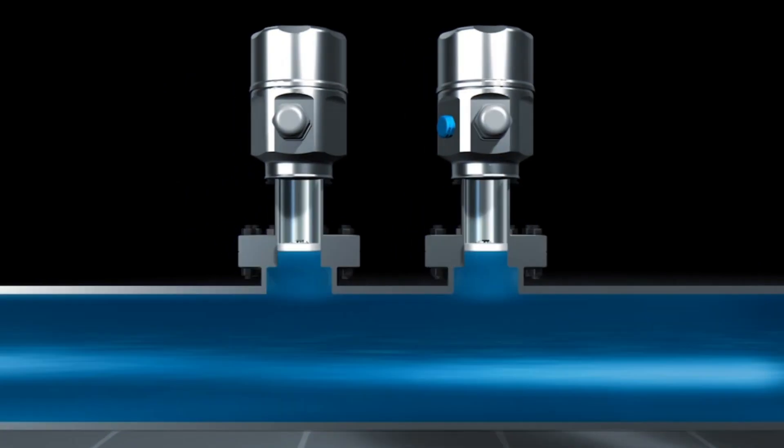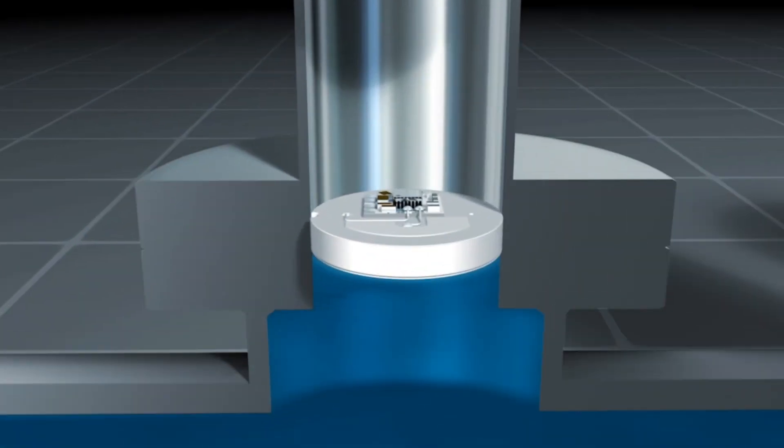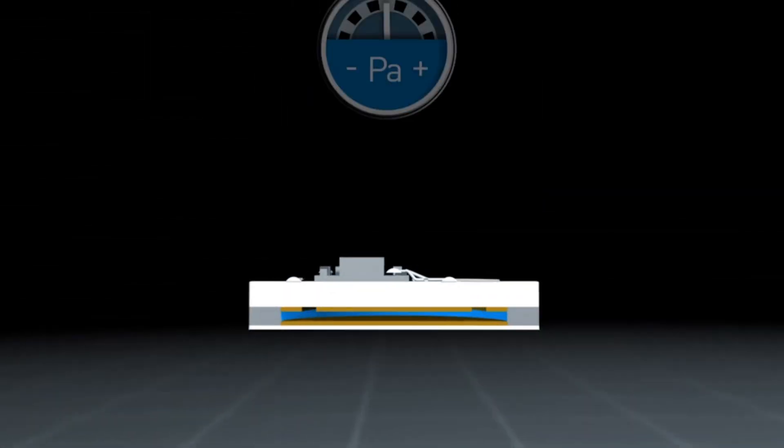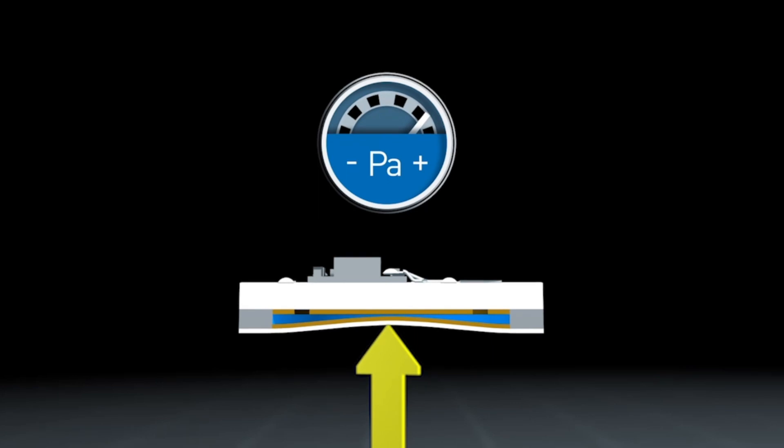Pressures can be measured continually in a pipe flooded with a liquid. We will have a closer look at the difference of an absolute pressure cell and a gauge pressure cell using the example of a ceramic cell. In a ceramic cell, an electrically conductive material is applied to a ceramic substrate, thus forming a capacitor. As pressure is applied, the diaphragm deforms and causes a change in capacitance.